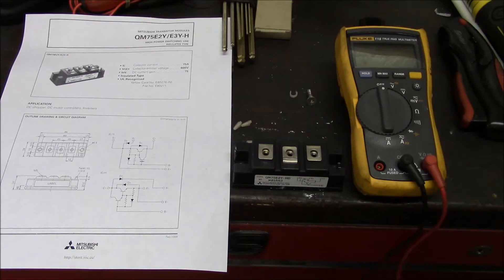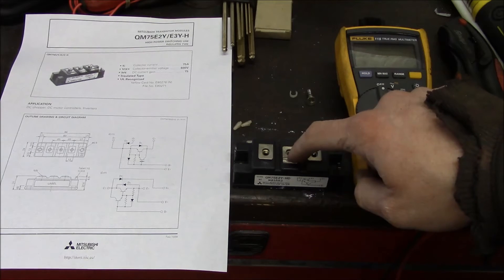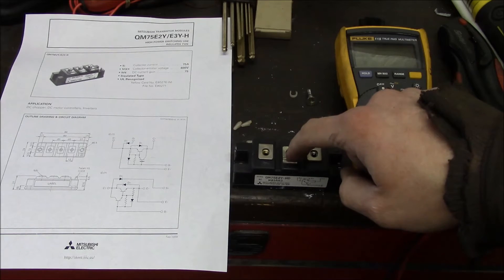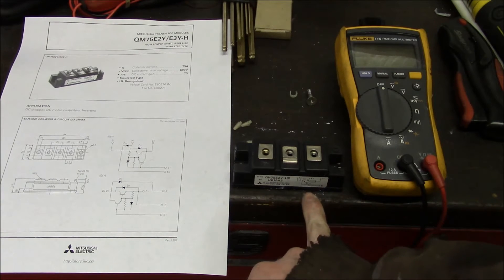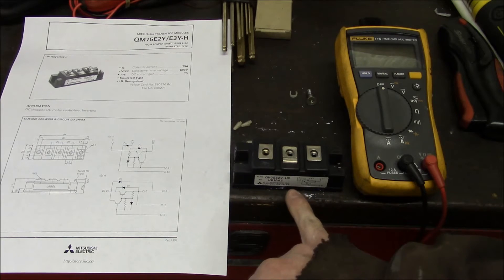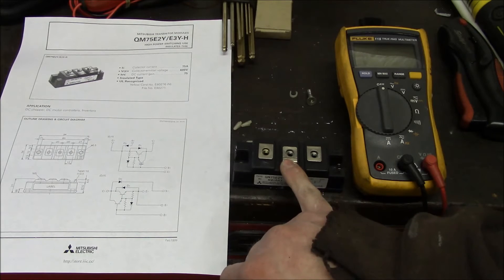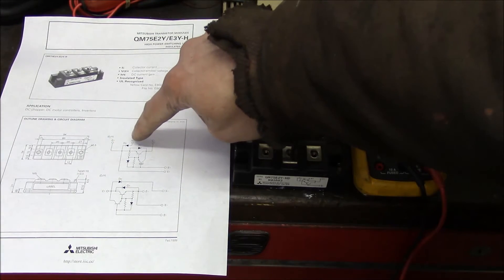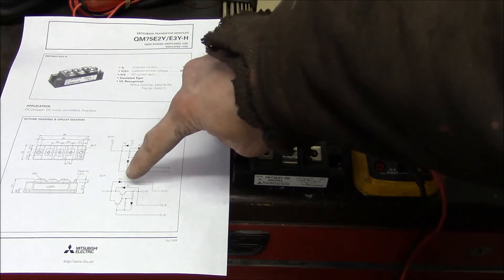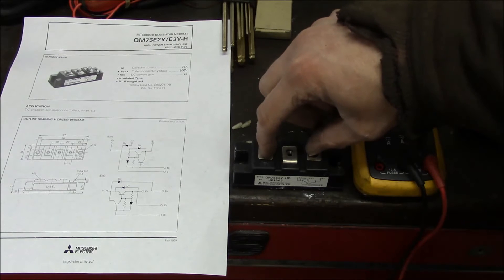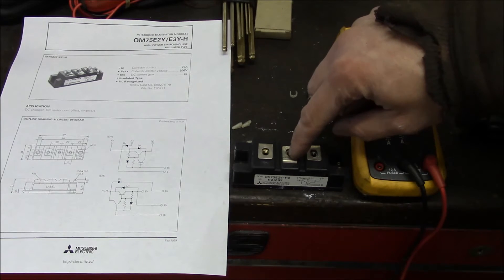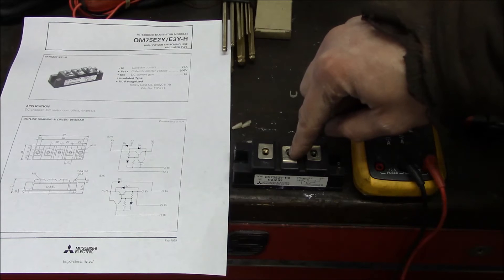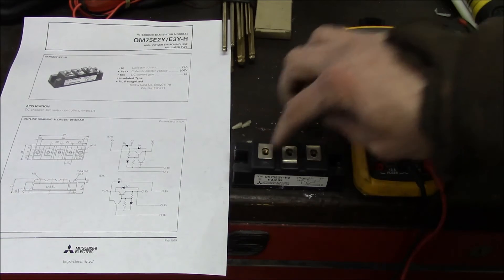All right, so this is the culprit that I replaced. This is what was causing all the problems in that Yaskawa spindle drive. So this is a Mitsubishi QM75E2Y-HD. And this is the data sheet for it. So it's basically just a Darlington transistor. So it's a small transistor that turns on a large transistor. And there's a 2Y and a 3Y. And it's the same housing, but the only difference is the direction, basically, of the diode.